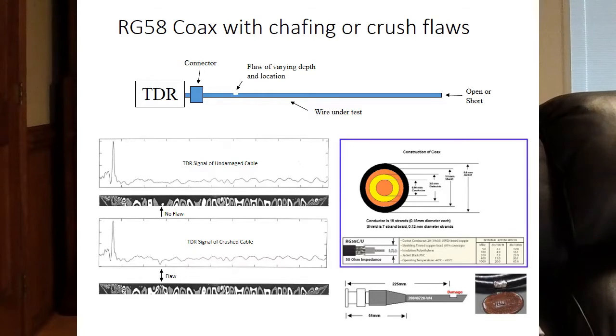Right? What we do is we take that time domain signal and perform a mathematical operation on it called a wavelet transform, and then we get a time scale image, and the way that we render that is sort of a black and white contour plot, and those quite often look like fingerprints, so we call them wavelet fingerprints. And then the idea is to find shapes in the fingerprints that correspond to the flaws that you're after, and then you can search the images for those shapes, and the position of the image in the time scale image allows you to identify how far along the wire the fault is.